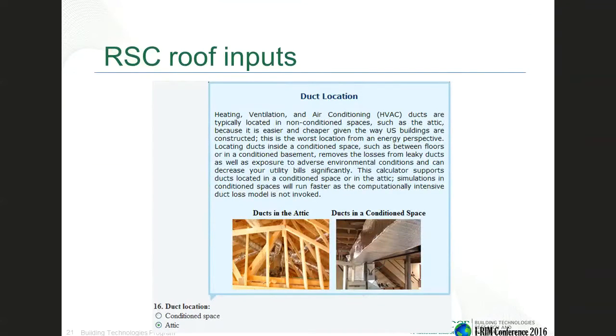Also, the duct location — even though it's generally the worst place to put them, we always put ducts in the attic because it's time efficient from a construction standpoint. The problem is that you have leakage and you're cooling the air and putting it through these ducts, but your attic can be swelteringly hot in southern climates — all that leakage is just zapping all the energy you put into creating that cool air. We have ducts in the attic as the default, but we can also model ducts in the conditioned space — like a basement or crawl space — which is generally more energy efficient because if you have duct leakage, it's actually going to cool the space rather than the outdoors.